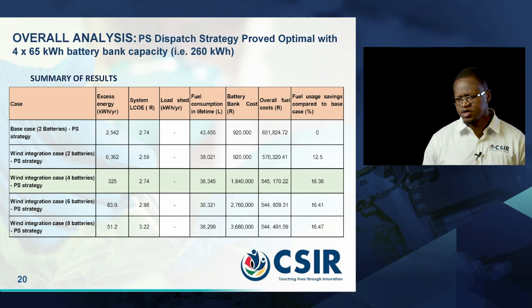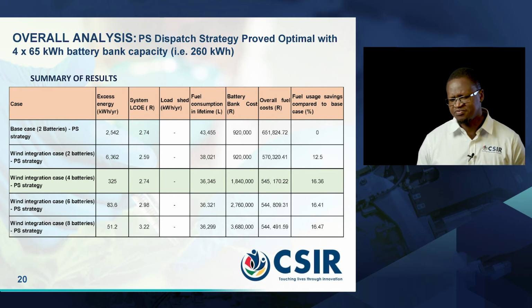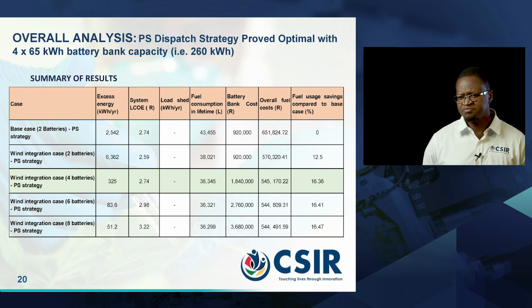And further on, we looked at different sizes of batteries, 4 batteries, 6 batteries, up to 8 batteries, integrating this with the predictive dispatch strategy. From the results, we found that 4 batteries with the predictive dispatch strategy would be the optimal size of batteries required for this region when using a predictive dispatch strategy for generation dispatching.